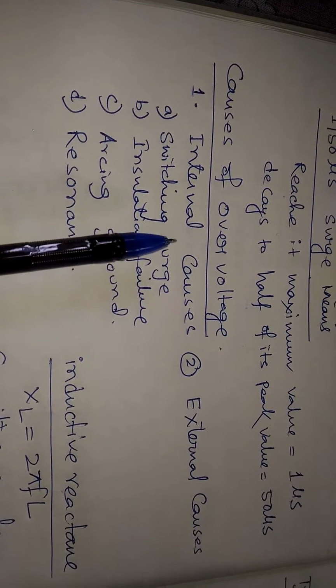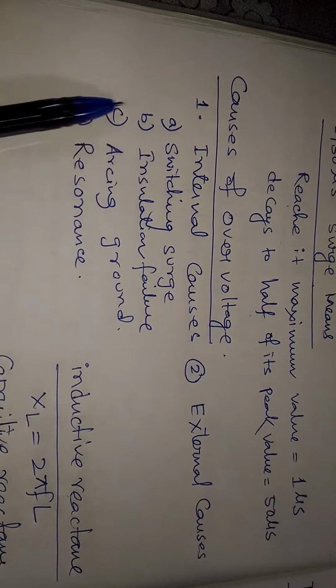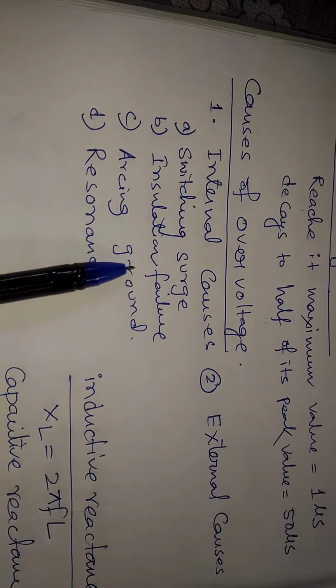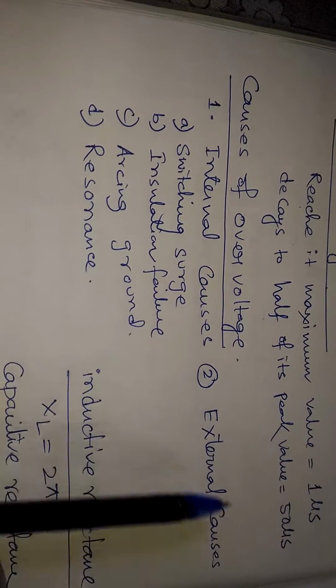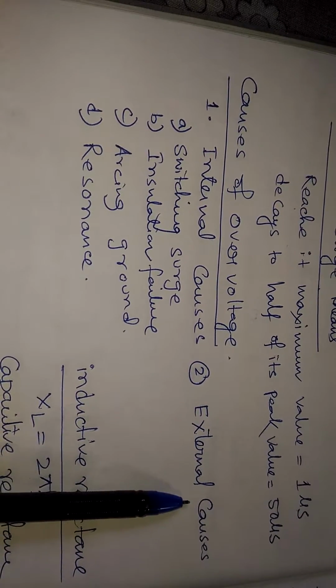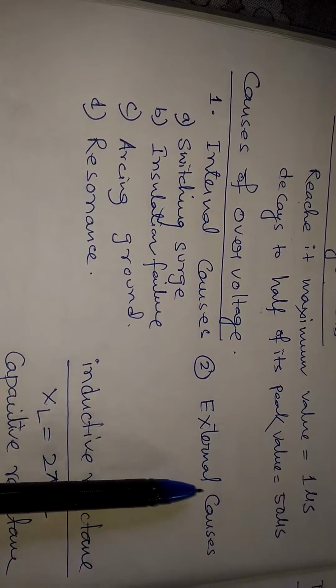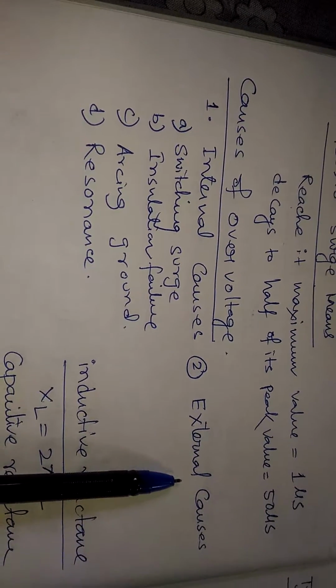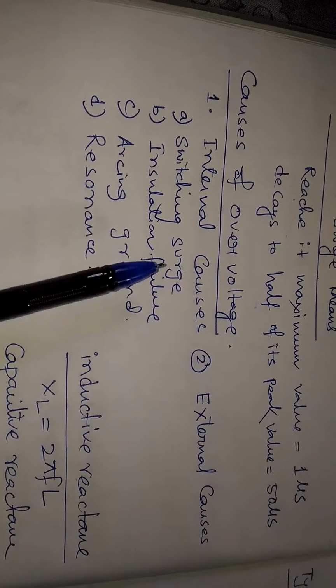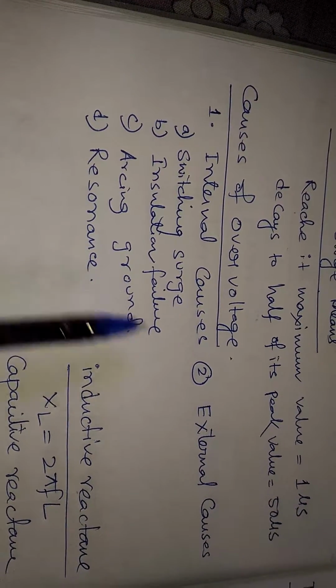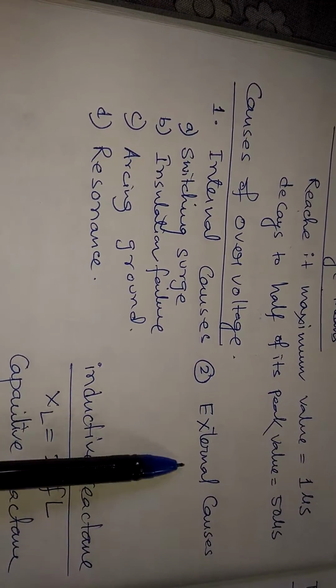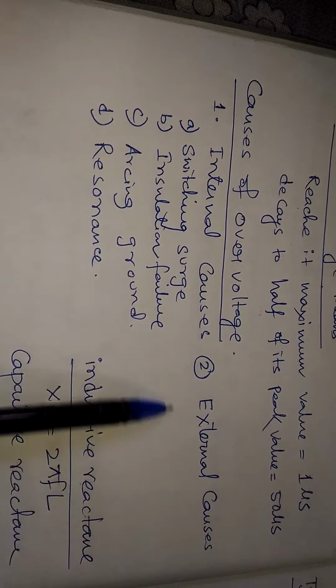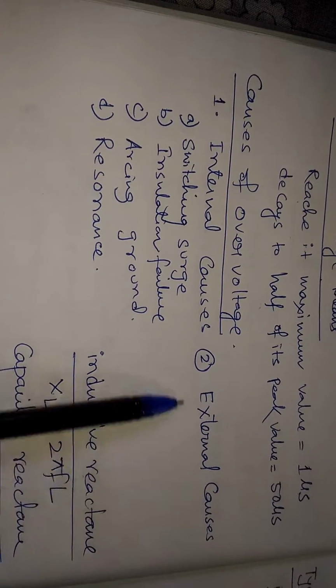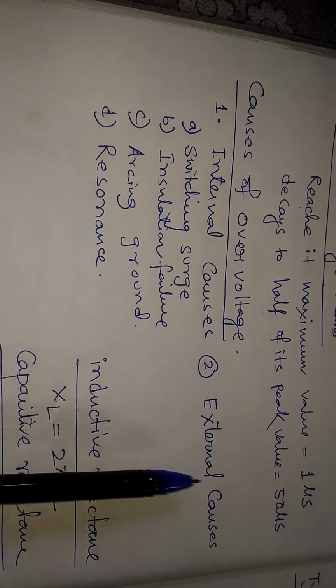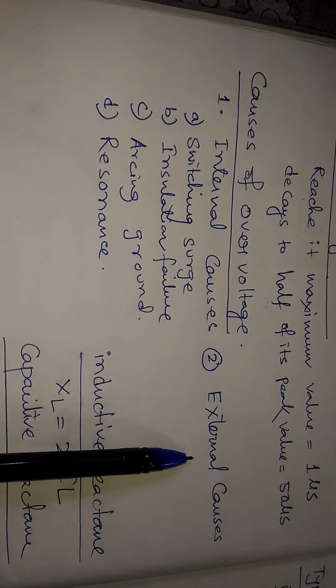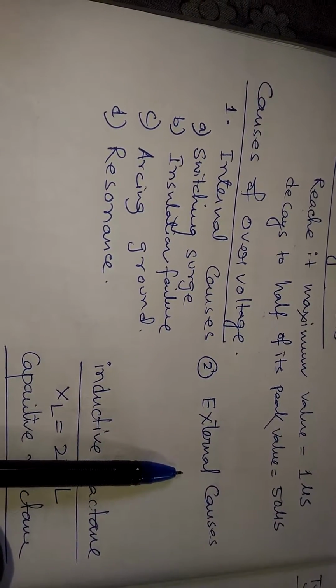For internal causes, the effect on the apparatus or equipment is not very harmful, but external causes have a very harmful and dangerous effect on the device. So we have to use protective devices against the external causes. Internal causes can be minimized by some instruments, but for external causes the voltage peak or magnitude is higher than for internal causes. So we have to provide protective instruments against the external cause, lightning.